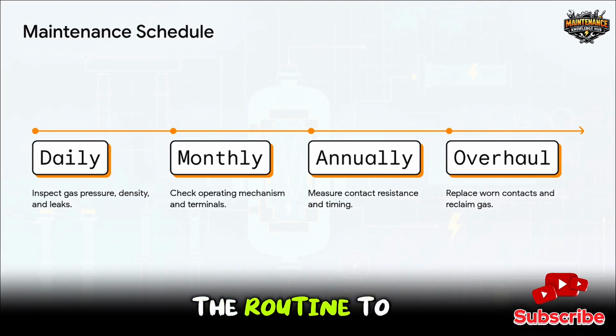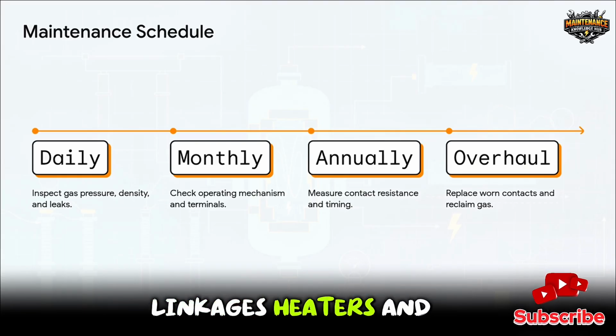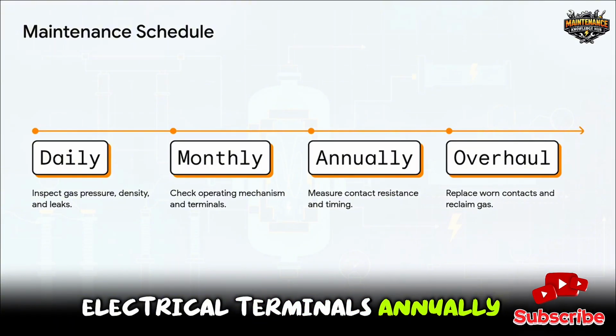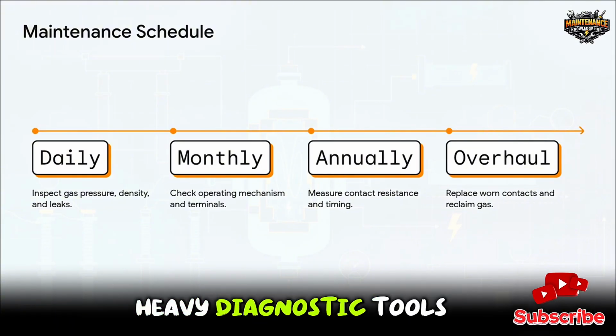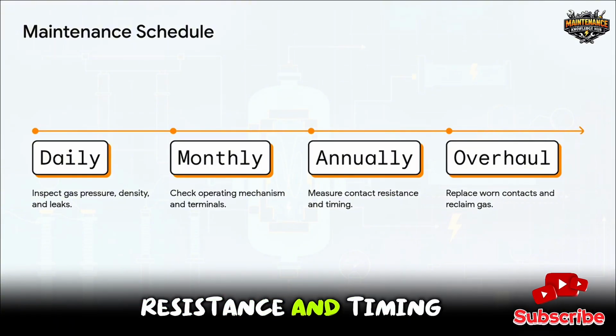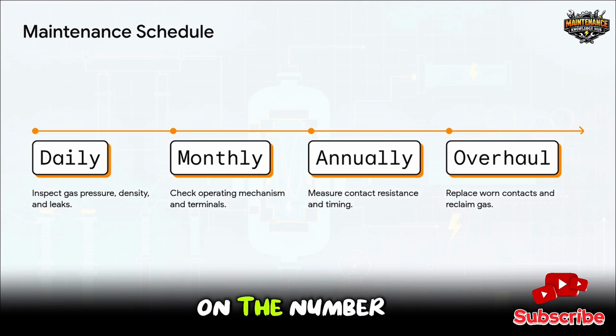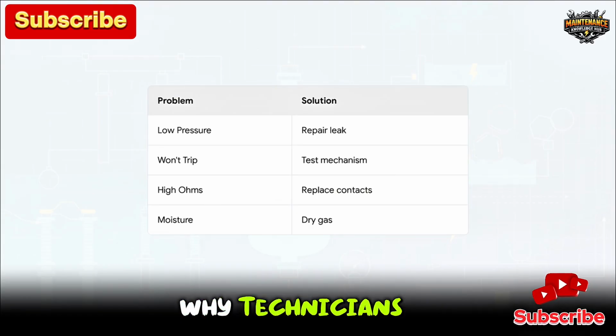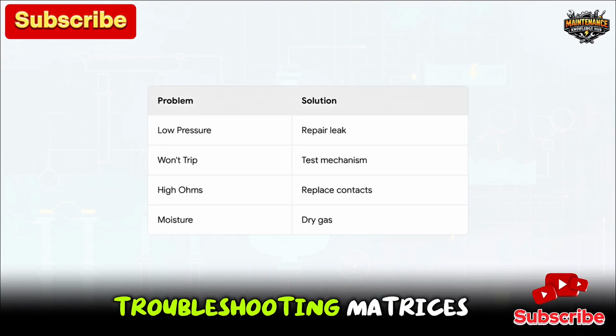Monthly, they step up the routine to inspect the mechanical linkages, heaters, and electrical terminals. Annually, that's when the heavy diagnostic tools come out to measure contact resistance and timing. And finally, based on the number of operations, the breaker undergoes a major overhaul. This is a massive teardown where worn contacts are replaced, seals are swapped out, and the SF₆ gas is carefully reclaimed and refilled.